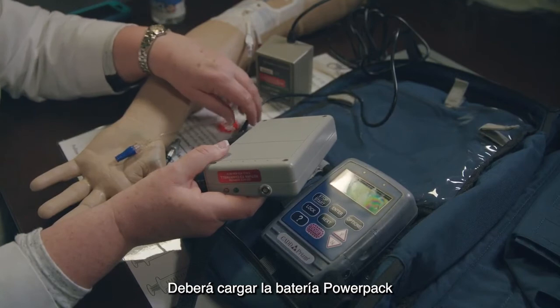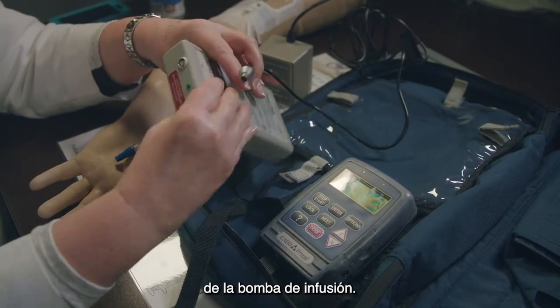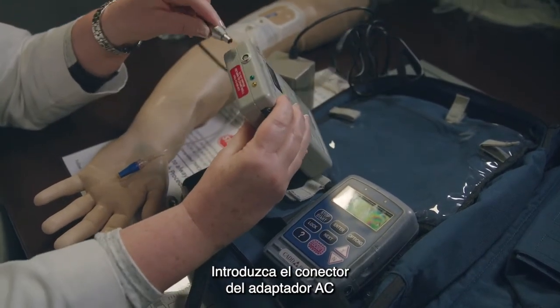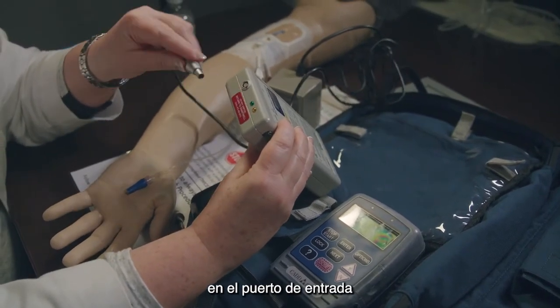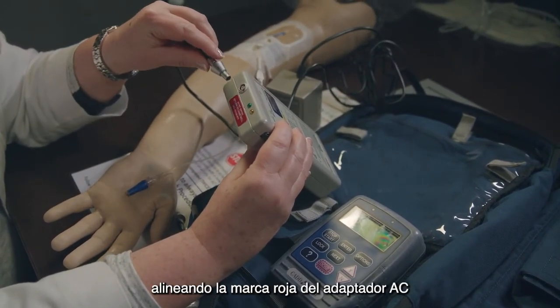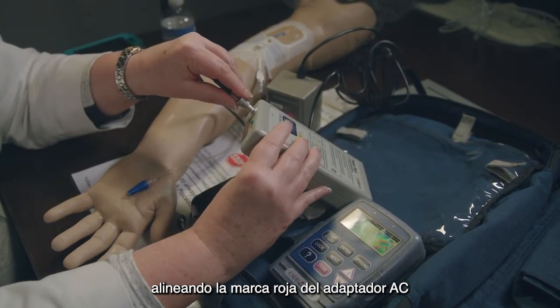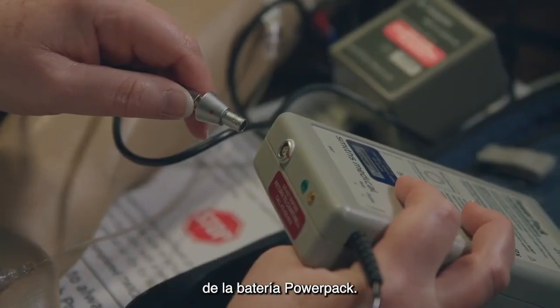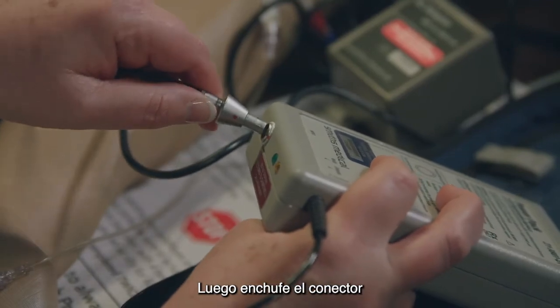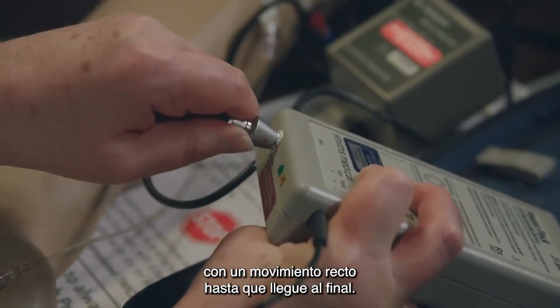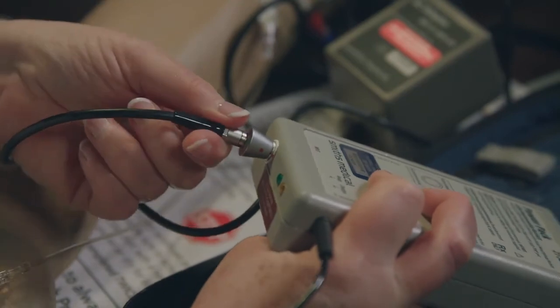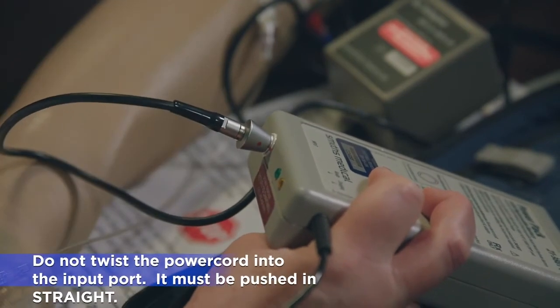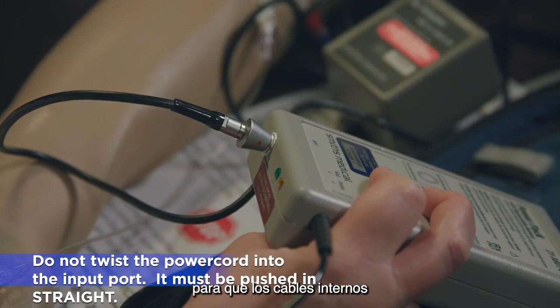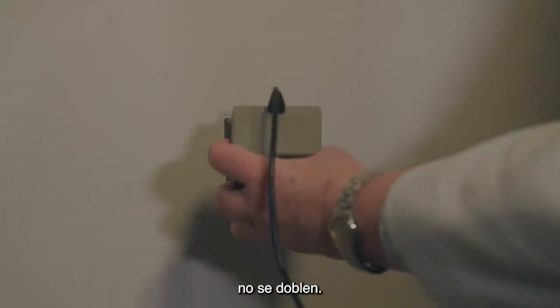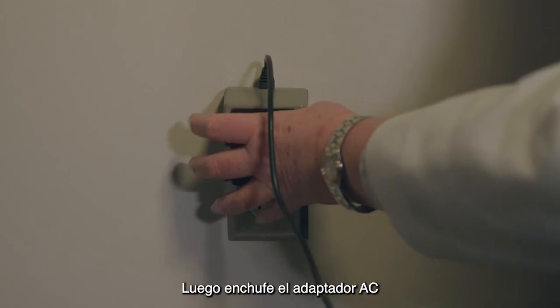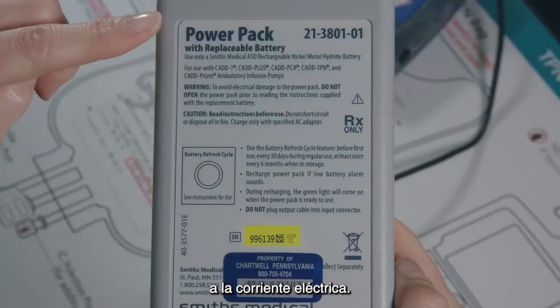You will need to charge your power pack once it is disconnected from your infusion pump. Insert the AC adapter connector into the power pack input port by lining up the red mark on the power AC adapter and the red mark on the power pack input port. Then, push the connector fully into the power pack in a straight motion until it stops. Do not twist or turn the connector. The cord must be pushed in straight so you do not bend the wires inside the cord. Then plug the AC adapter into the wall outlet.